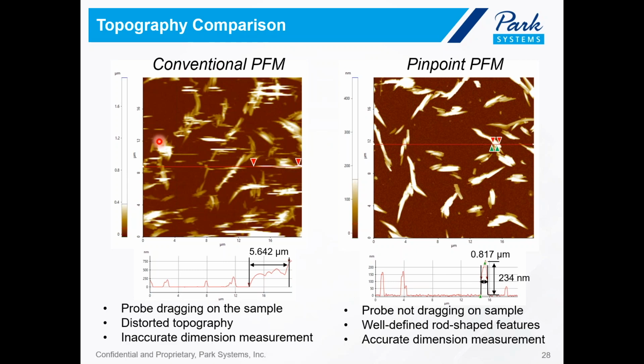From the conventional PFM imaging conditions, imaging artifacts can be seen throughout the entire scan area, indicating that the probe was scratching and dragging on the sample. We have distorted topography, and accurate dimension measurement of the features was very difficult, nearly impossible. To give you an example, here we draw a line profile along the red line, and here is the actual line profile. If we want to measure the width or the length of the rod, here is what we measure, 5.6 micron, which is obviously not the actual length of the rod, but an indication that the probe is dragging on the sample. So that is not an accurate measurement.